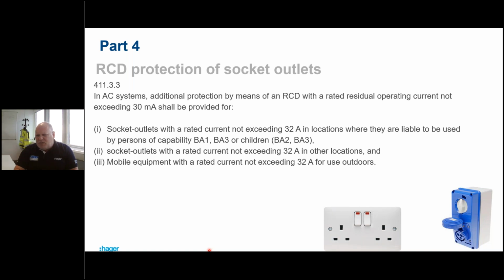Then we've got number 2, which pretty much covers every other kind of socket we might have. Socket outlets, okay, in other locations. Then we get number 3, mobile equipment, rated current not exceeding 32 amps for use outdoors. Okay, so that's pretty much got socket outlets sewn up. Okay, so what if we've got an installation, maybe a server room, where we don't want RCD protection on our socket outlets? We used to be able to label up a socket that said fridge freezer only, okay? We didn't need to protect it.